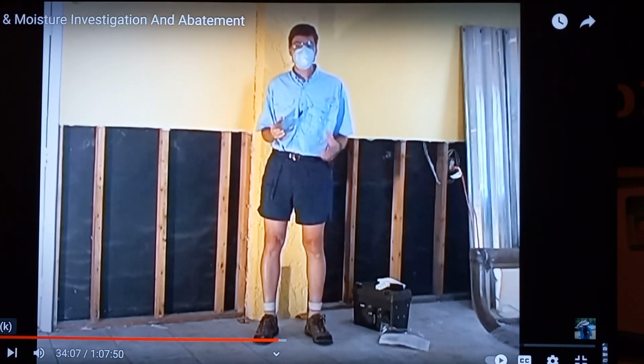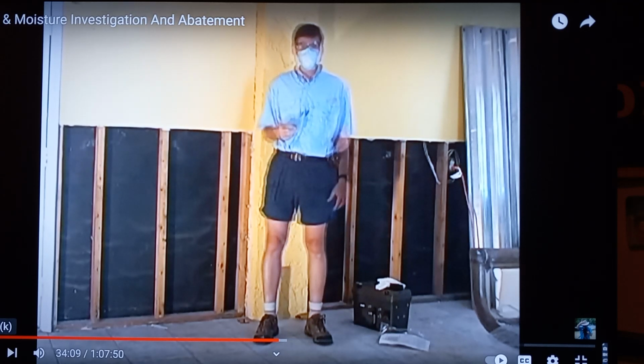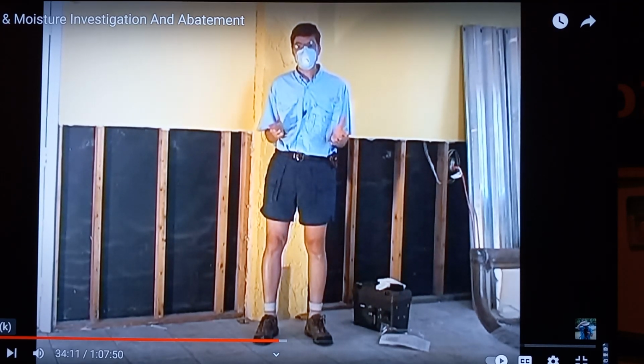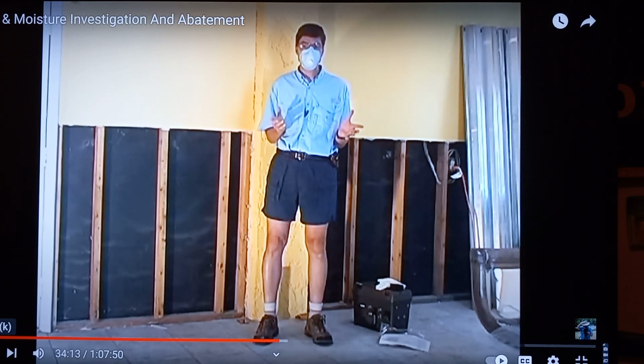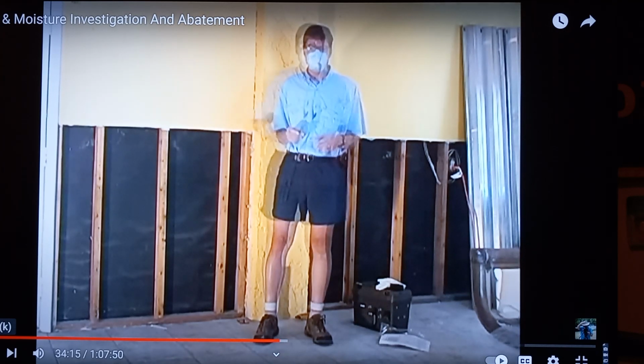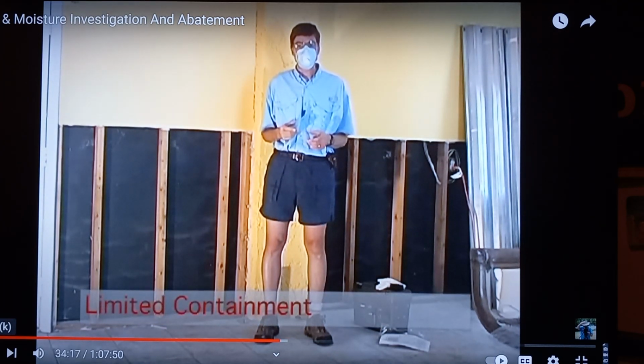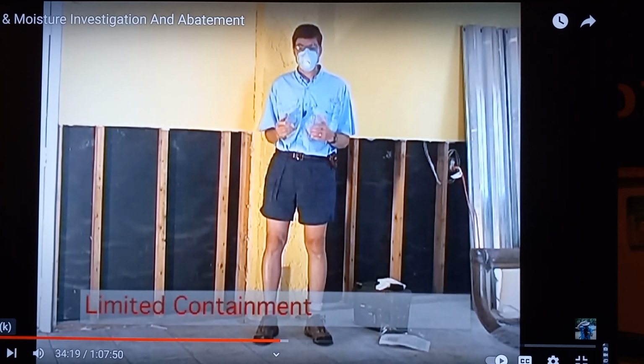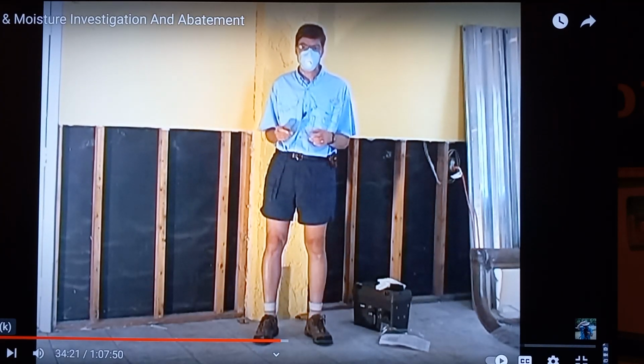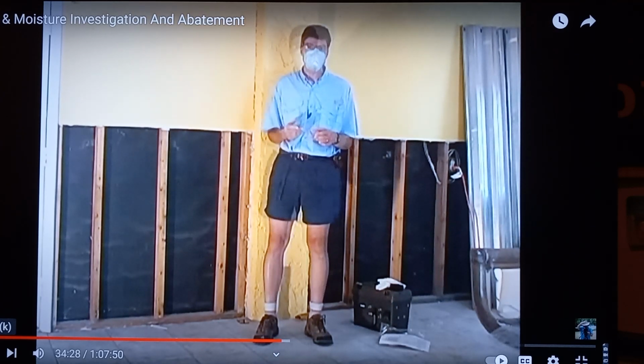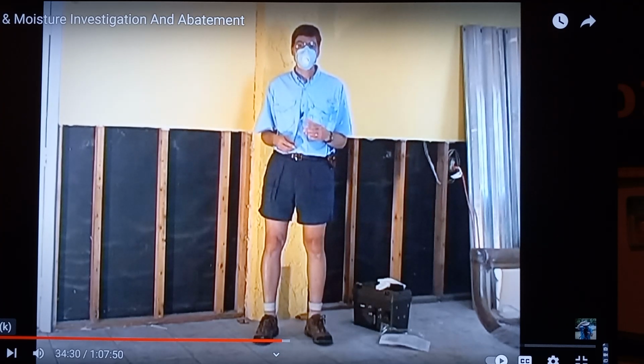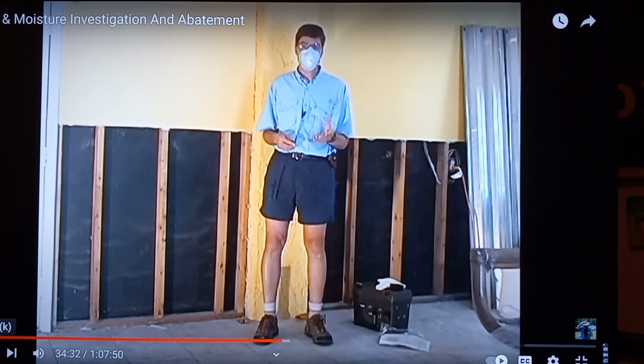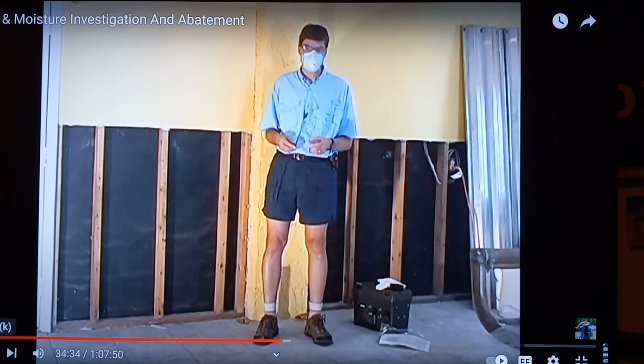The next area that's going to be reviewed is containment. This is using a polyethylene sheet from floor to ceiling around the affected area. Limited containment would include a slit entry and covering flap. The area is maintained under negative pressure and HEPA filtered fanning. Seal off the supply and return vents in the contaminated area.